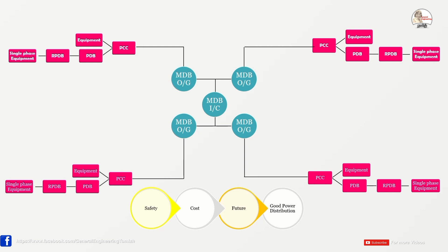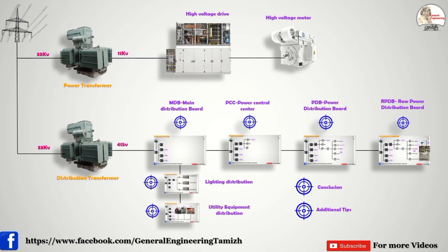The third tip is future concern. When installing any panels — MDB, PCC, PDB — always keep extra spare feeders. You cannot predict plant expansion. Extra loads or motors may be added suddenly. If spare feeders are not planned, you will have to go for a completely separate distribution with a separate transformer and separate MDB even for a small load increase. By maintaining spare feeders, you avoid this. If you follow these procedures and tips, your power distribution system will be in good shape. The next video will cover how the power distribution system is controlled by breakers and what types of breakers are available in manufacturing industries.